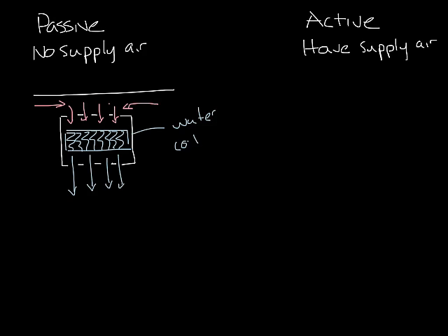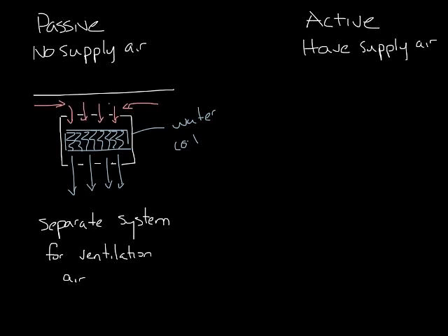As I said, there's no supply air on a passive chilled beam, so you have to have a separate system providing ventilation air to meet your ASHRAE 62.1 requirements. Passive chilled beams are not as common as active chilled beams in the U.S., so let's move on to active chilled beams.